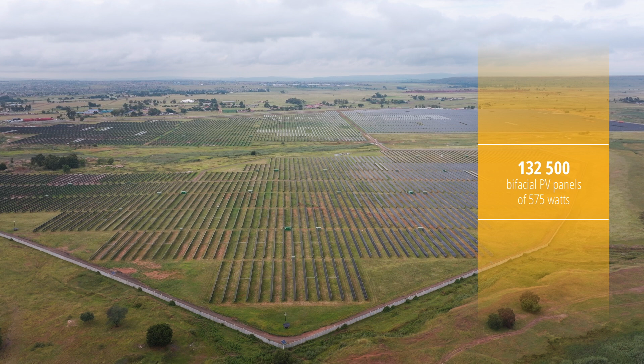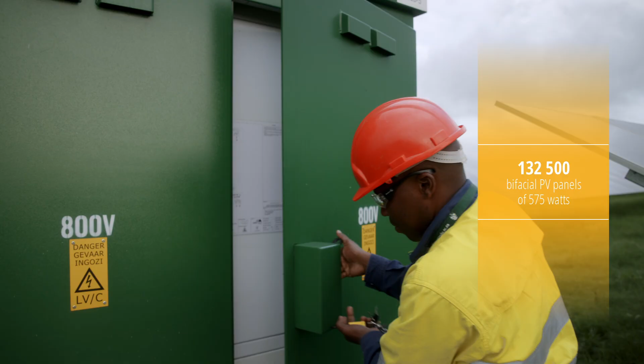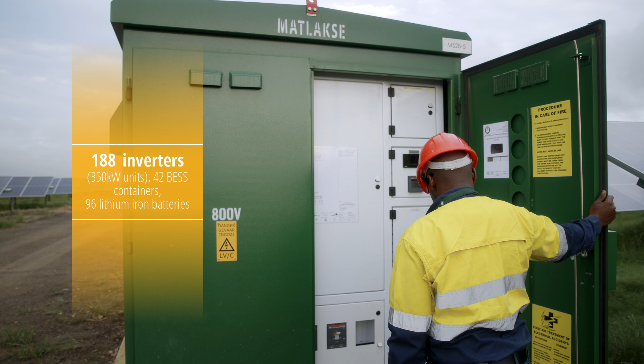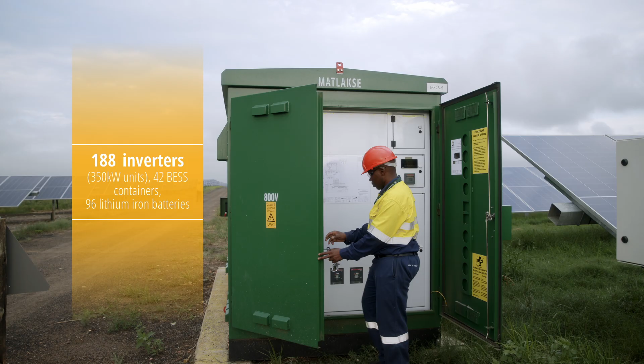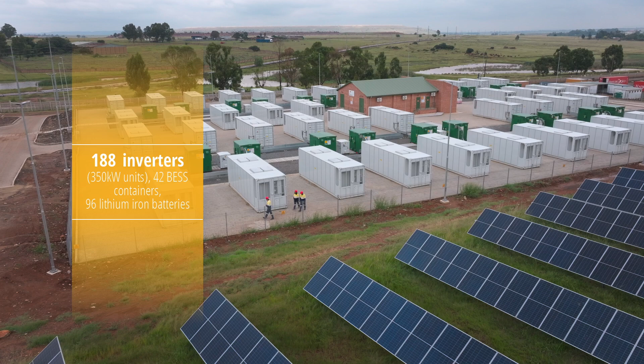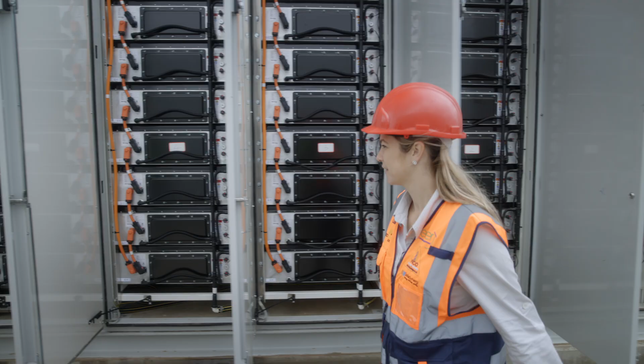The solar plant consists of 132,500 panels, feeding through 188 inverters. These are 350 kilowatt units, and those inverters then feed into 42 BESS, or battery energy storage containers. Each of these containers has 96 lithium-ion batteries. This is the first project that has BESS, PV, and a load behind the grid, and is exporting into the grid.